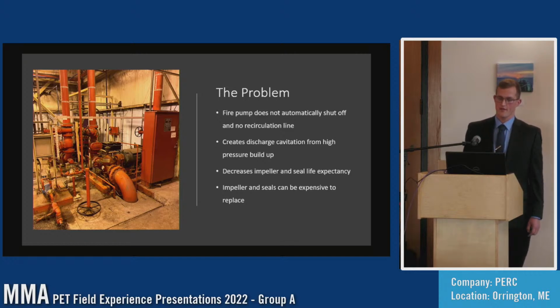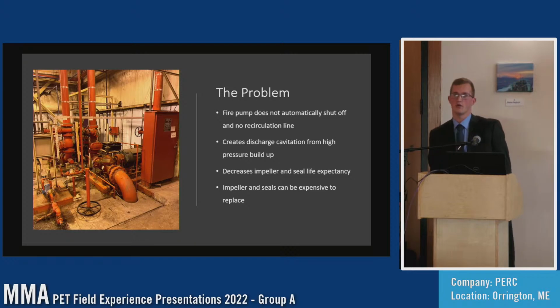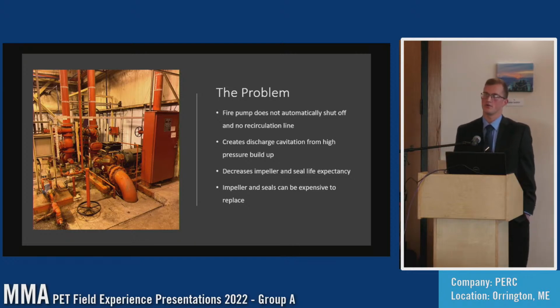A large fire pump is used that produces 1,500 gallons per minute, and there are 3 pumps in this system total, all in parallel to each other. The smaller pump, the jockey pump, is just for pressurizing the dead line that is not being used, with no water flowing through it. The big pump is the main electrical pump that I was focusing on. This pump turns on automatically once it senses a large enough pressure drop in the piping system where the jockey pump cannot handle it.